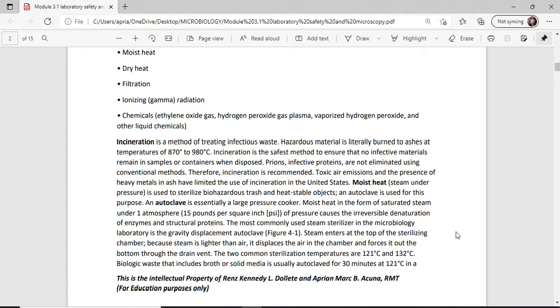The most commonly used steam sterilizer in the microbiology laboratory is the gravity displacement autoclave. Steam enters at the top of the chamber because it is lighter than air. It displaces the air in the chamber and forces it out of the bottom drain vent.